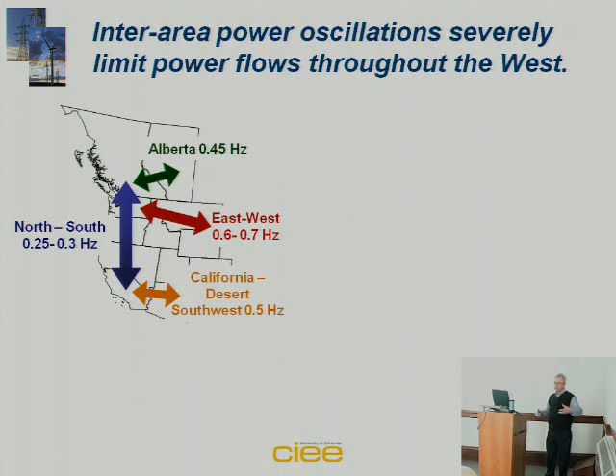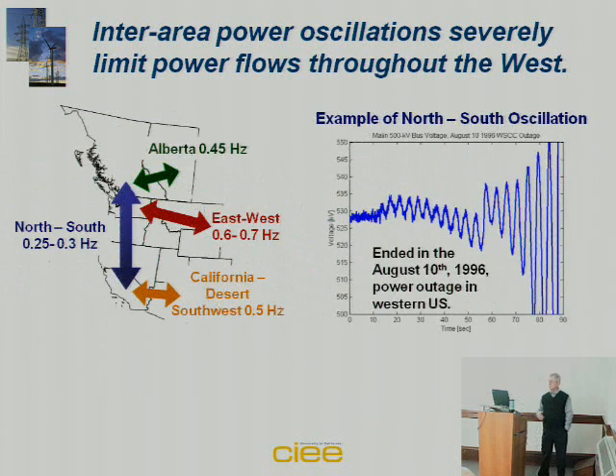My metaphor for it is trying to carry a big, shallow bowl of water, and you walk someplace with it, and it starts to slosh, and so you try to stop it, so you stop, but sometimes it won't stop. It just keeps right on sloshing, and the water sloshes out. Well, a similar kind of thing can happen in which the power can start these oscillations, and they go undamped, and indeed they go haywire. And in this case, this was on August 10th, 1996. This is the actual precursor of the outage where a line touched a tree. It was caused by this oscillation that went on for an hour or two before the line actually overheated and touched the tree. These oscillations are major problems.